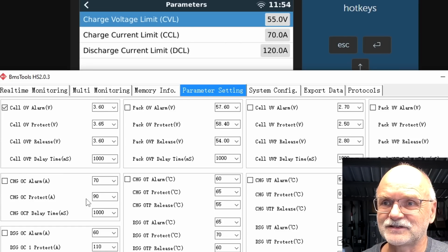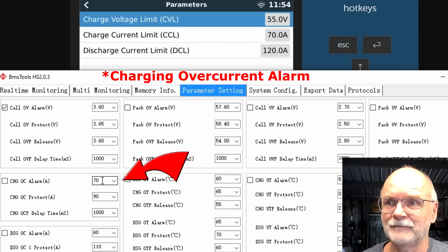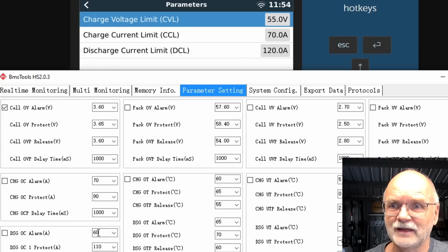The master sits on 70 amps charging current, and this is exactly what it shows up here. The discharge alarm sits on 60 amps, but this one is now doubled because we've got two batteries. But it actually doesn't double the CCL, the charge current limit.